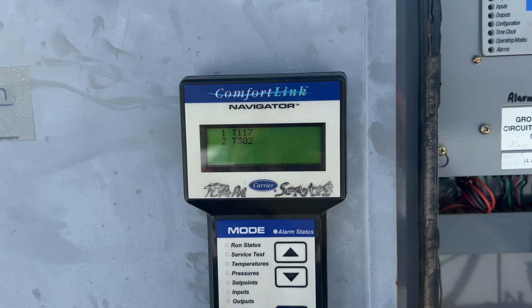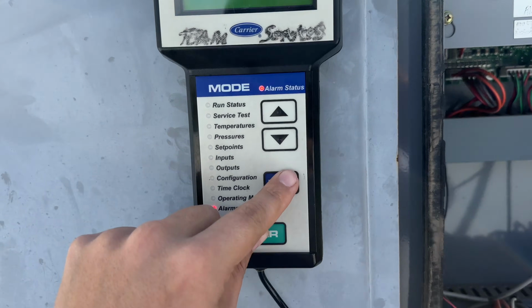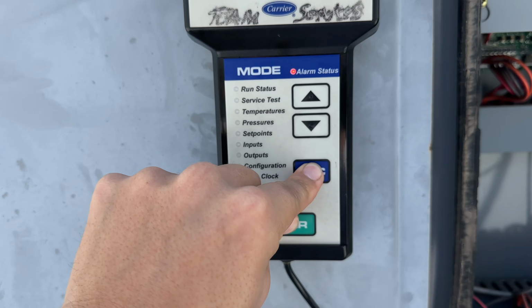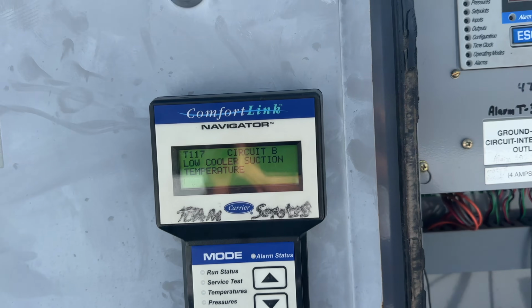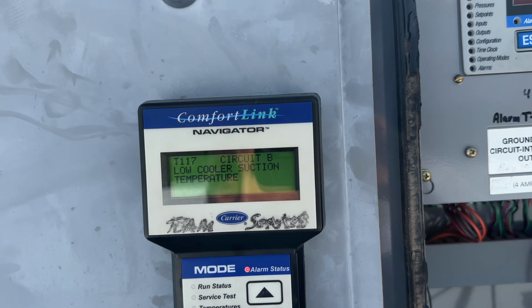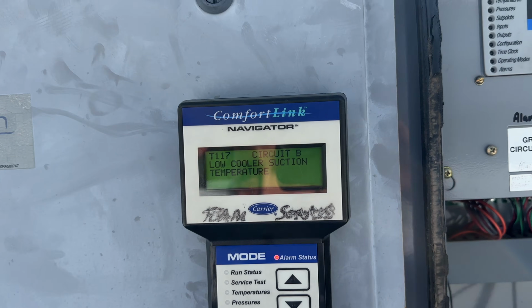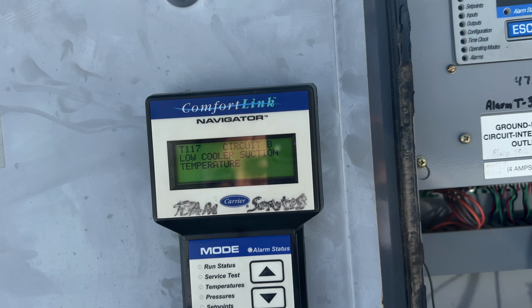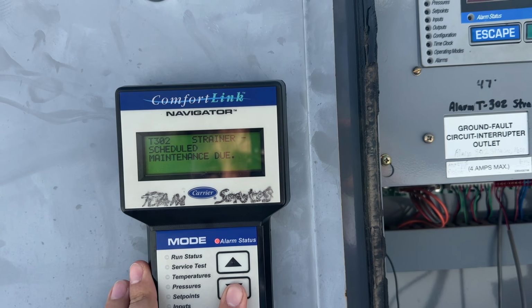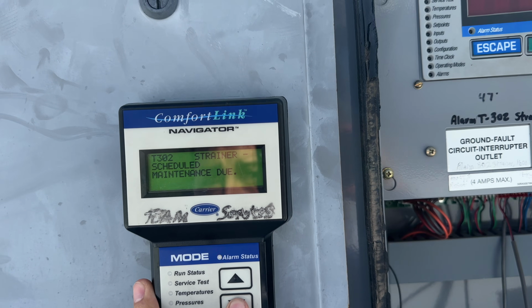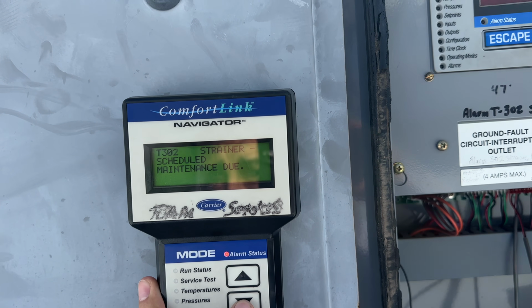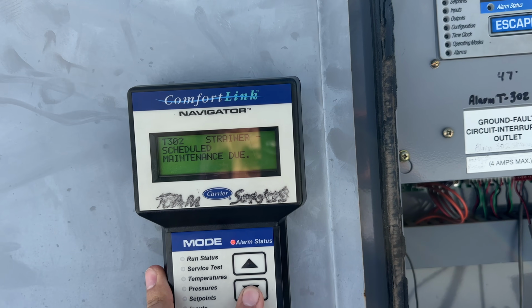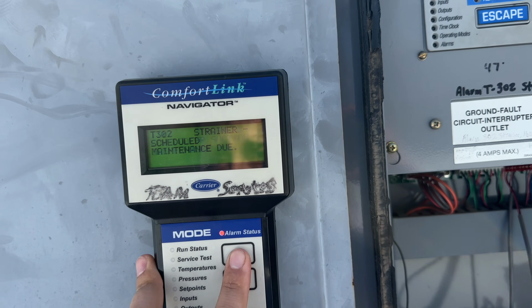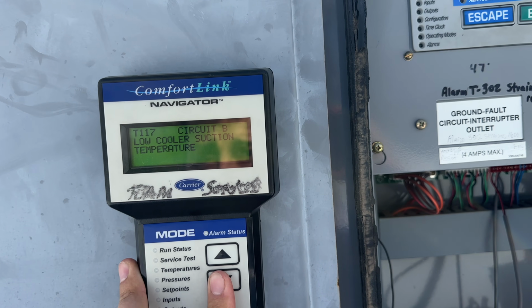T117, enter. If you hit enter and escape, you can actually read the entire alarm. T117 is low cooler suction temperature, circuit B. I think that has something to do with the actual pumping off. Then there's a 302, scheduled maintenance due. So those are the only two alarms.